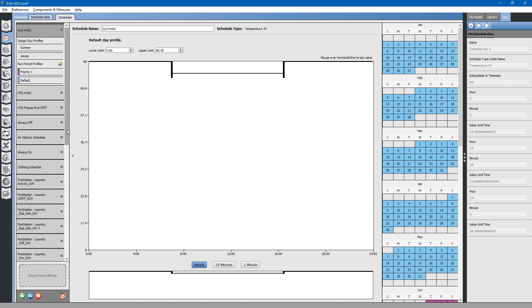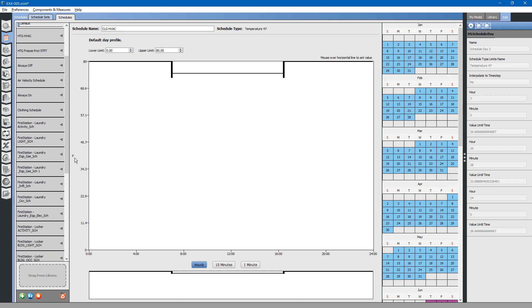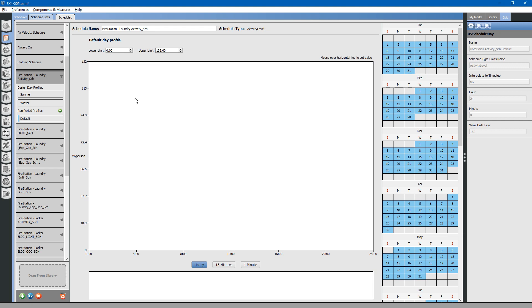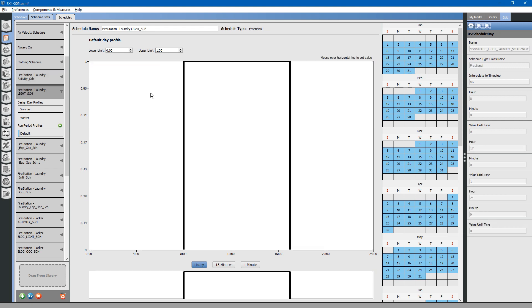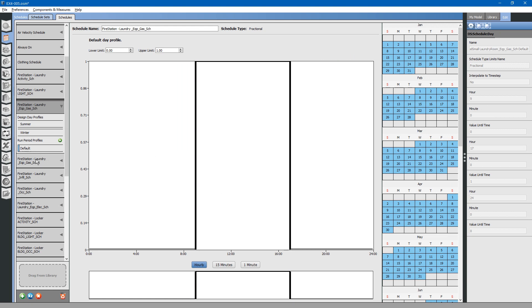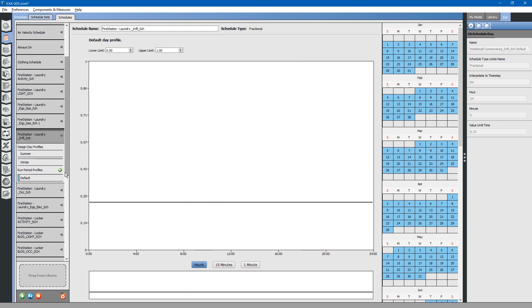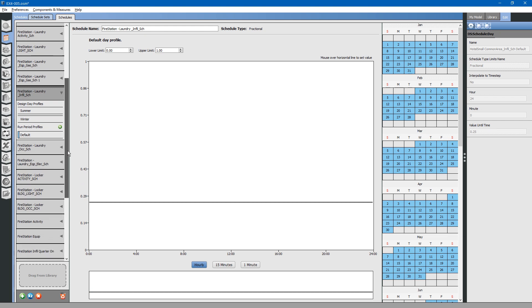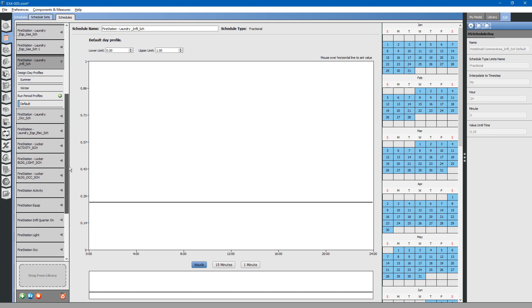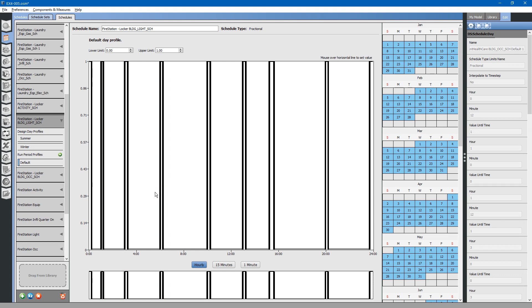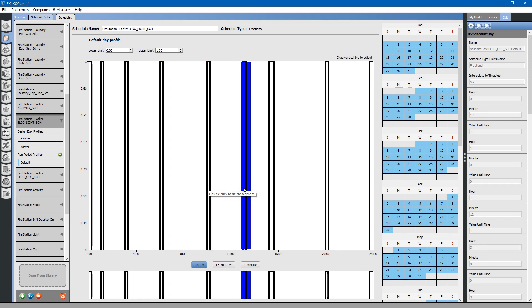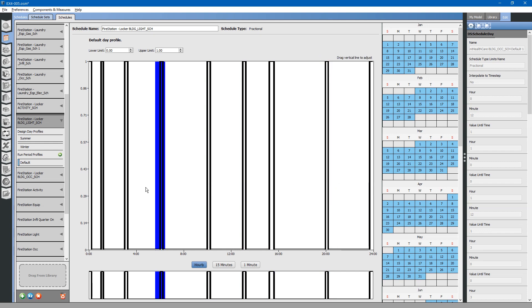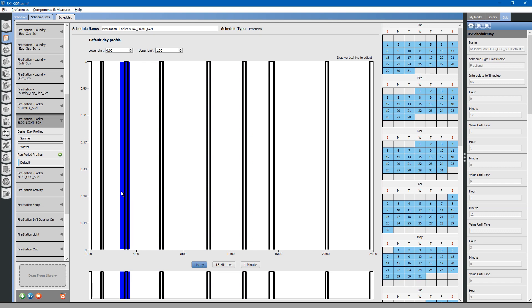That is an example of schedules. There are other different types of schedules. Laundry activity schedules - this is basically saying how many watts the people in the laundry room are putting out for heat. Lighting schedules - this says the lights go off at night time, they turn on at 8 in the morning, then they shut down at about 5 o'clock in the afternoon. Gas schedules are similar. Infiltration schedules are a fractional schedule. This is a multiplier that is multiplied by the total space infiltration that is applicable. You will see that the locker room lighting goes on and off a lot in this schedule. This is probably because the firemen are going out to various different calls throughout the day and night. They have to use the locker room to get suited up.